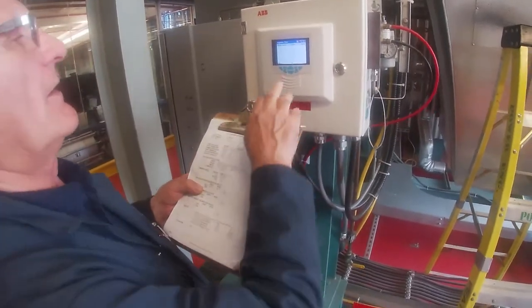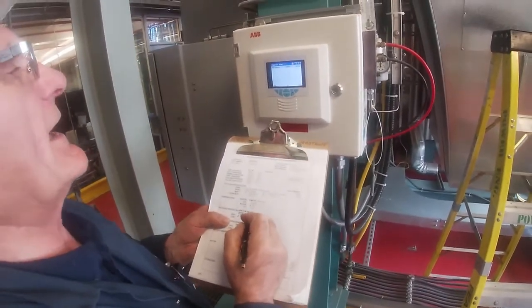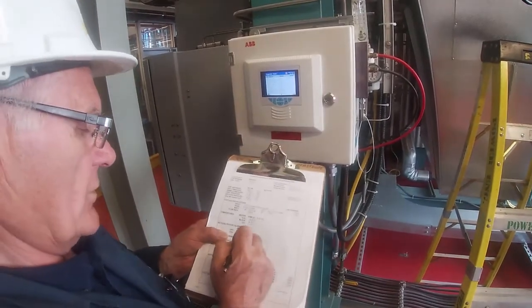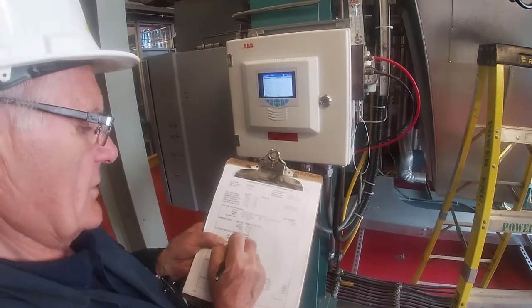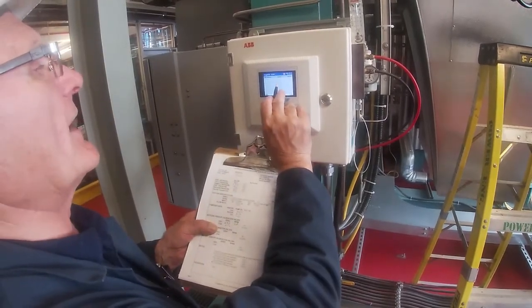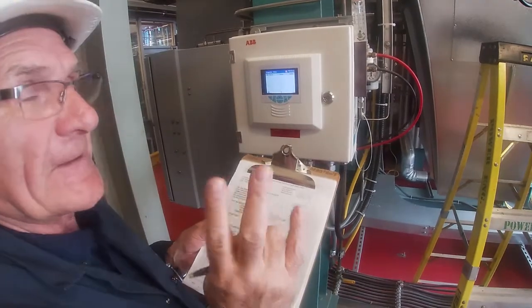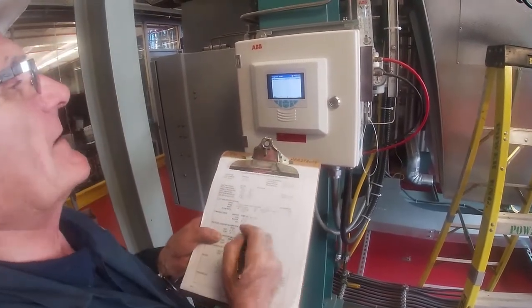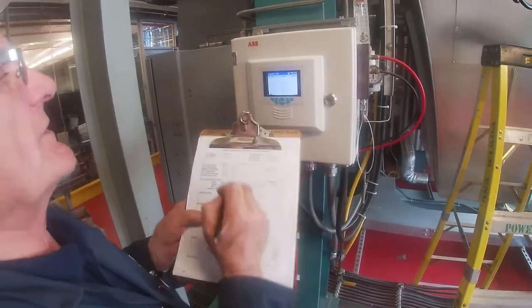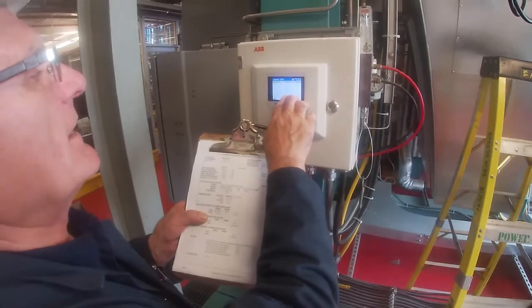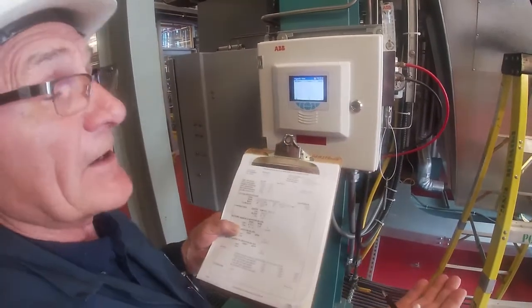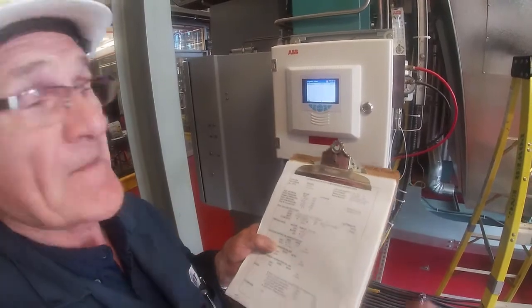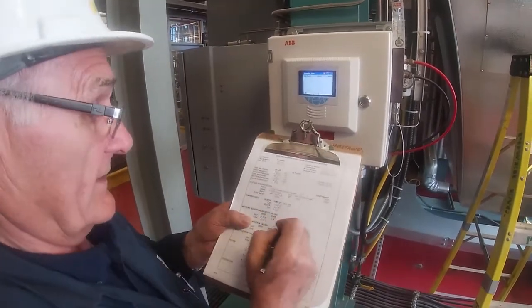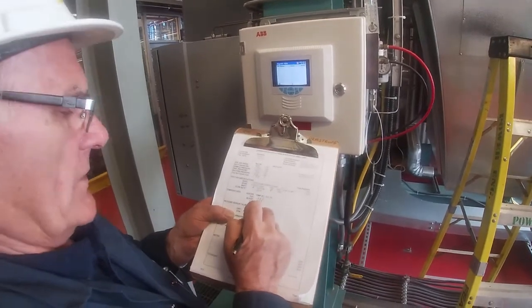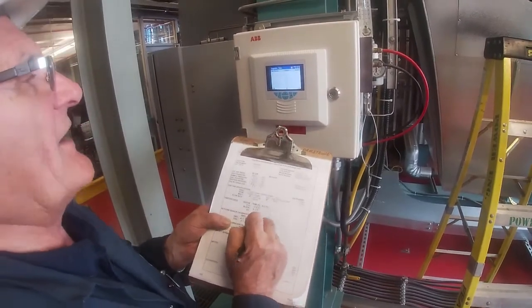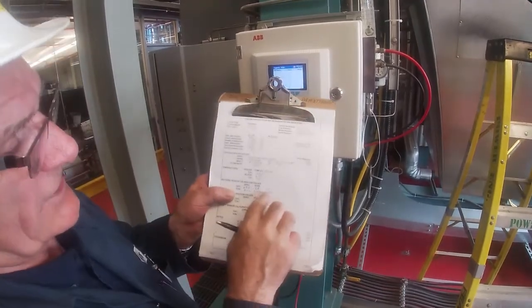So now I've got to go get the COE values, and that's on the next page. The COE zero is 0.42. And the span is a temperature difference. Remember there were two sensors in there and it's looking at the temperature difference across them, and it's actually in degrees Fahrenheit. It's sitting at 3.23. That's not very much. That's the temperature difference for 2,000 parts per million CO, so it's next to nothing. And it doesn't have any units beside it, so there are no units on the form.